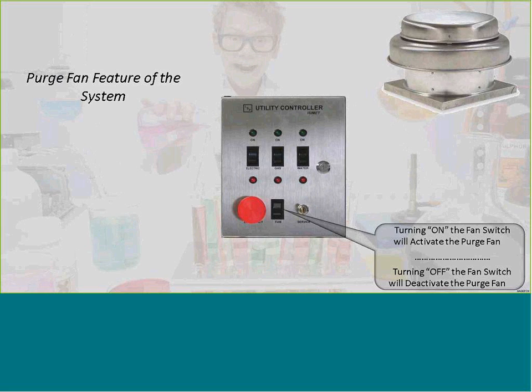Now, the fan can be programmed to normal operation, where you're just turning it on because you want to evacuate the odors from the experiment you're doing, or you can have a high-low fan situation where, when a panic button is hit, you want to withdraw all that chemical out quickly, so you can have it on a high-speed fan to boost that fan up and out.